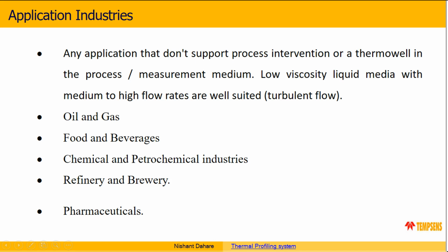So these sensors can be used in oil and gas industries, and in food and beverages, such as dairy products, where you want to measure the temperature of the milk inside a pipe. In refinery and brewery, in alcohol breweries, you need to check the temperature of the raw material inside the pipe, and also in pharmaceuticals. In all those industries, process contamination plays a huge role. So it eliminates process contamination, corrosion, and downtime. You don't need to shut down your process to install the sensor. You just need to clamp the sensor and take the readings.